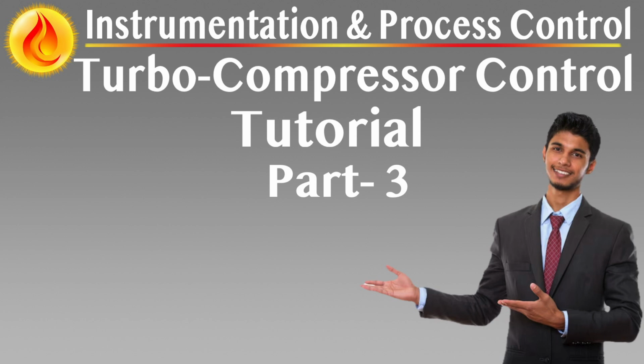Monitoring of operating conditions. Real-time feedback from auxiliary systems is captured and displayed on the human-machine interface, HMI, and relayed to the distributed control system, DCS. This includes parameters like seal gas pressures and flows, lube oil temperature and pressure, nitrogen buffer systems, filter differential pressures, and cooling water status if applicable.